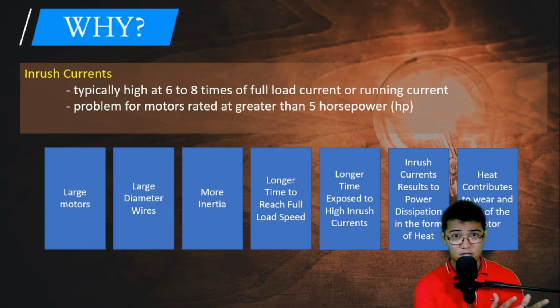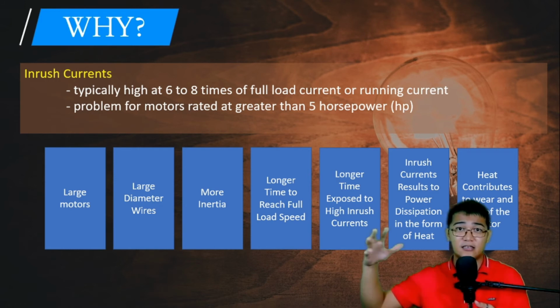So again, large motors, mas malalaki yung wires na ginamit. Mas malalaki yung wires, mas magiging mabigat. Magiging mabigat, more inertia. Mahirapan tayong pagalawin. And because of that, it will take time for it to reach full load speed. Pag longer time to reach full load speed, mas expose yung ating coils or yung ating mga wires sa loob ng motor to high inrush currents. Because coils have resistances, it will incur power losses. So may kuryente na dumadaan sa coil, square niyan times the resistance of the coil, yun yung power losses dissipated as heat. At yung heat na yun yung sisira. So killing me softly yung nangyayari dito sa ating electric motor. So this is the reason why kailangan natin ng hindi lang direct online na electric motor starting methodology. Kailangan natin ng iba pa.